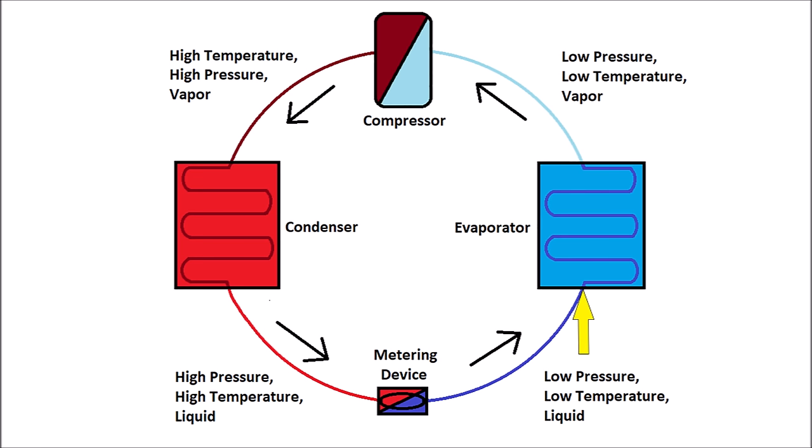Then the refrigerant enters the evaporator as a low pressure, low temperature liquid refrigerant. It absorbs heat energy while it's changing in state, and then it turns into a low pressure, low temperature vapor.